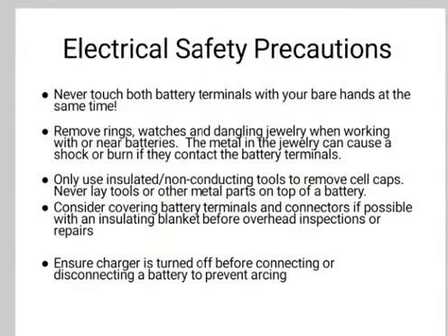Then next is electrical safety precautions. Never touch both battery terminals with bare hands at the same time. Remove the rings, watch and jewelry when working with or near batteries. The metal in the jewelry can cause a shock or burn if it contacts the battery terminals. Only use insulated non conducting tools to remove cell caps. Never lay tools or other metal parts on top of the battery. Consider covering battery terminals and connectors, if possible, with an insulated blanket before overhead inspection or repair.